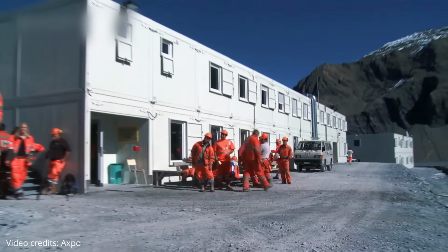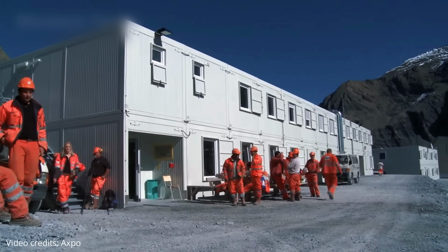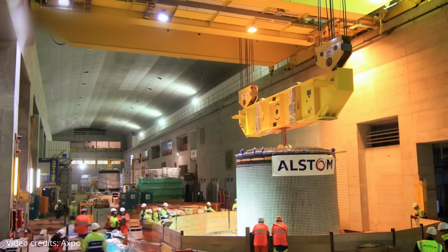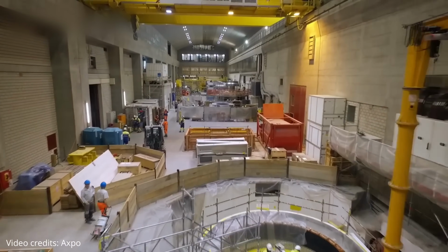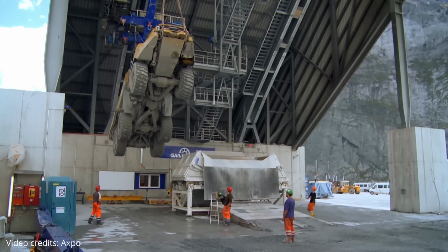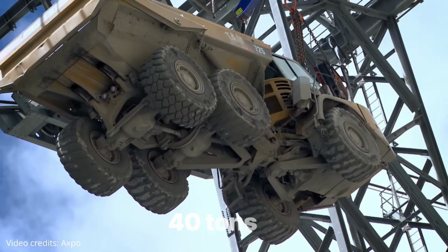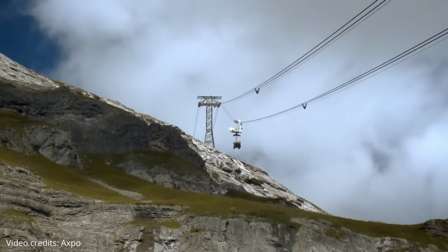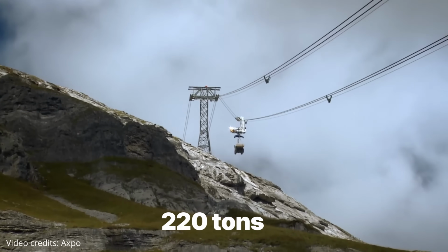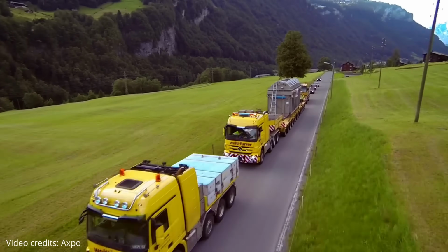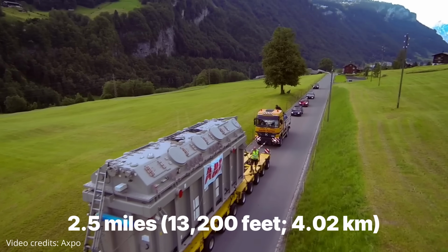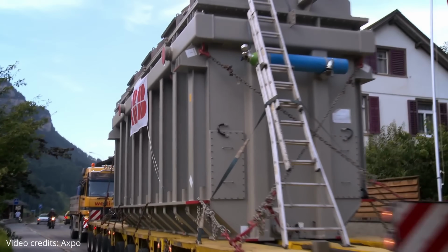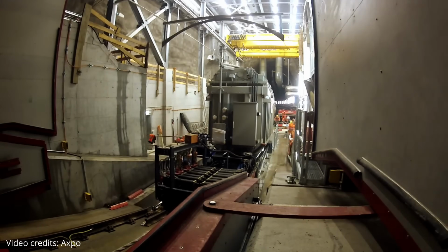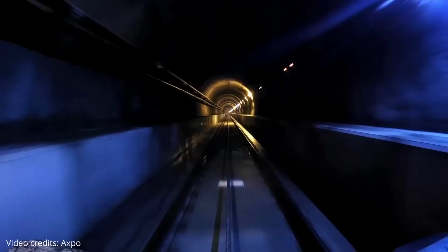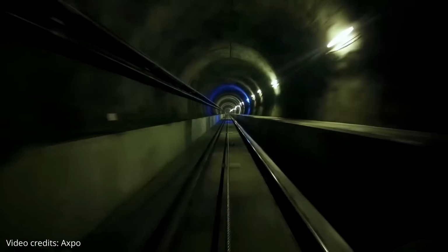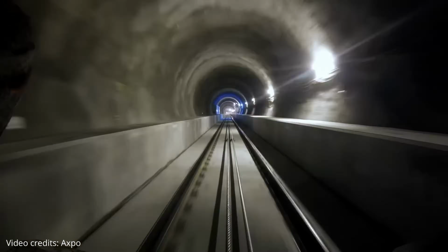Hundreds of workers cycled through the project over the course of construction, with major activity running round the clock from the Tierfeld base. Because the mountain's internal transport cable had a weight limit of 40 tons, and the 4 main transformers weighed 220 tons each, a separate underground cableway nearly 2.5 miles long had to be built specifically to carry the transformers to their final position inside the cavern. The funicular simply could not handle that load.